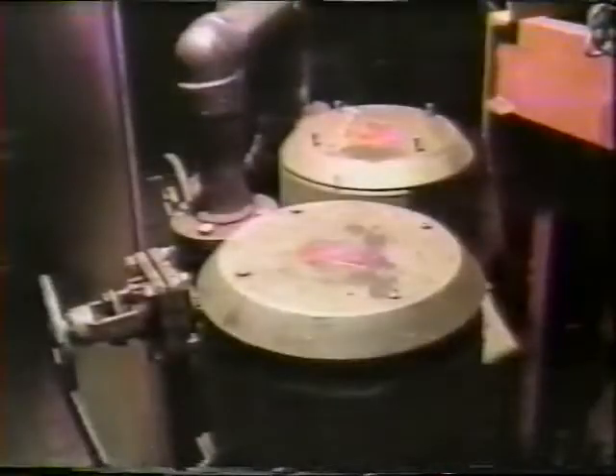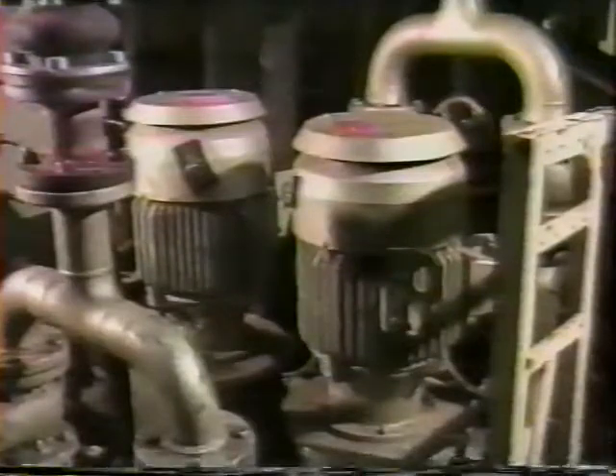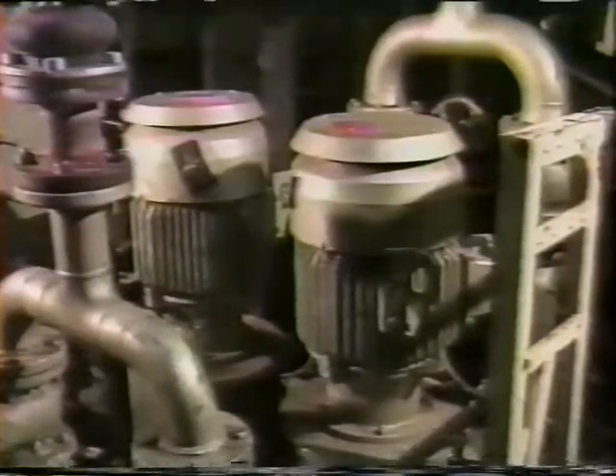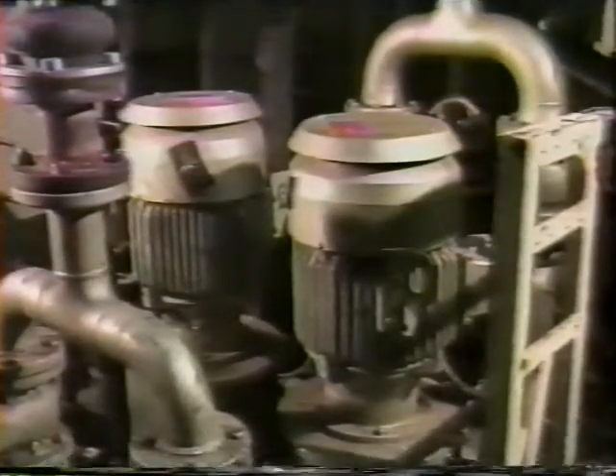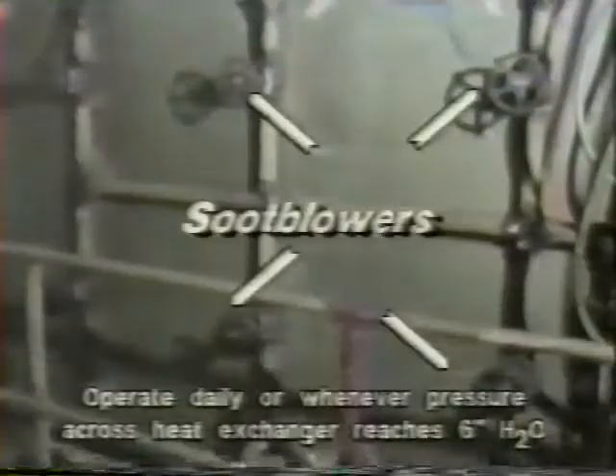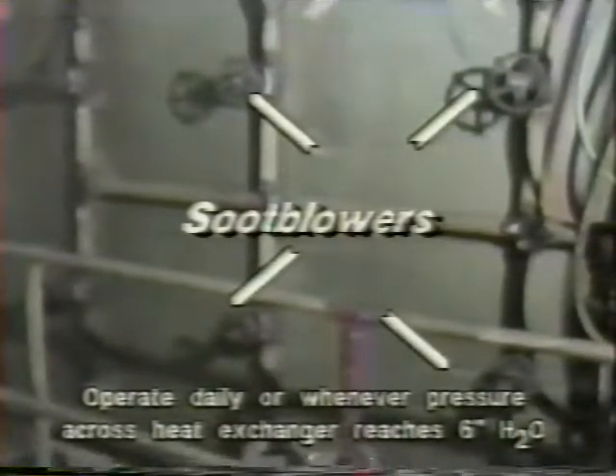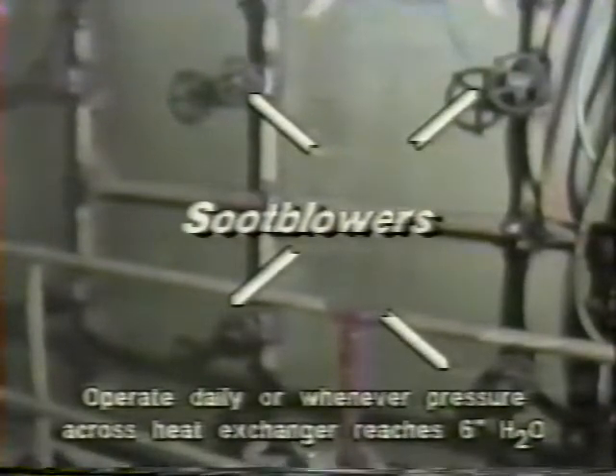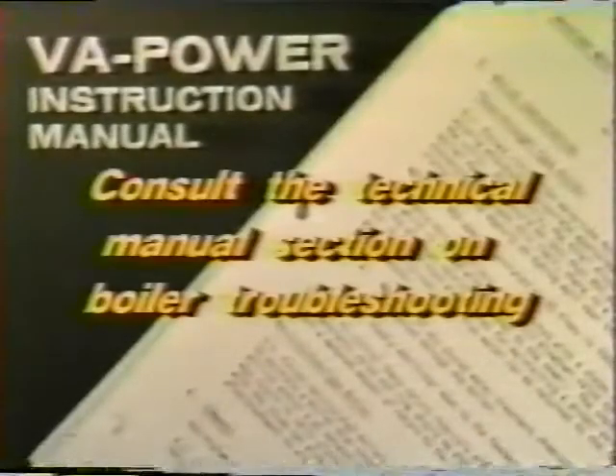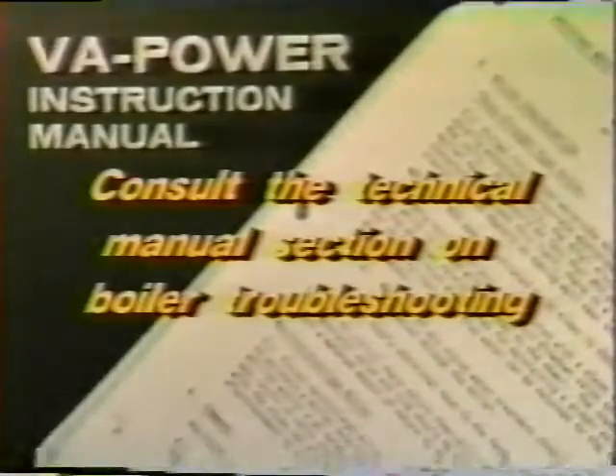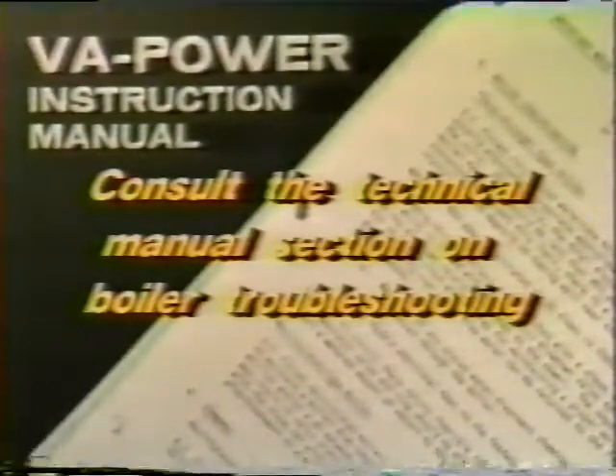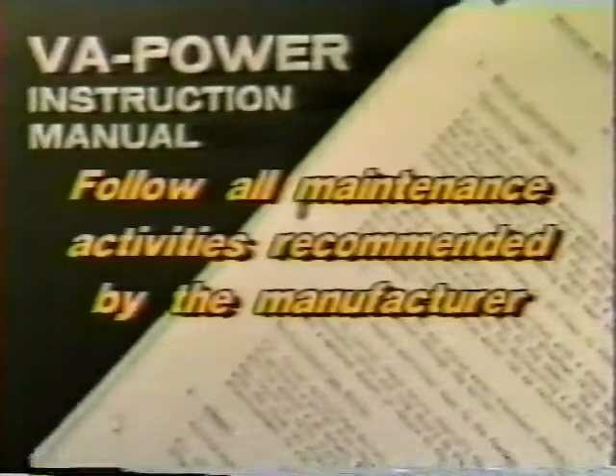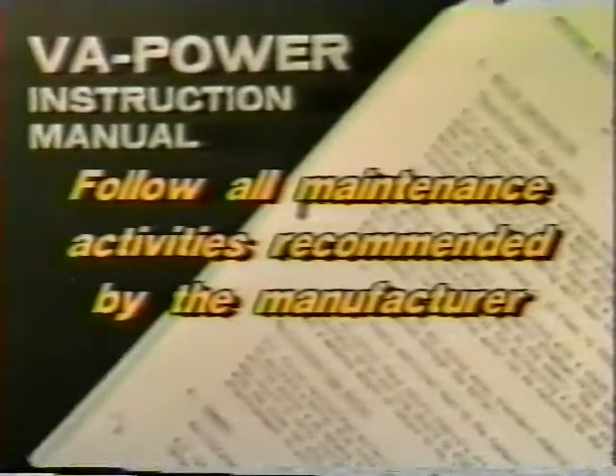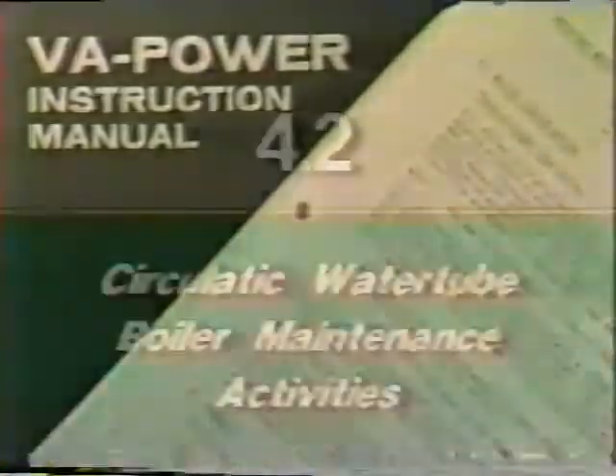Also, the number 1 and number 2 feed water pumps and recirculating pumps should be alternated so that each pump is kept in serviceable condition. Soot blowers on the boiler should be operated daily or whenever the pressure drop across the boiler heat exchanger reaches 6 inches of water. The tech manual contains a section on boiler troubleshooting that gives possible malfunction indicators along with probable cause of each malfunction. Carefully consult this section of the manual and follow all maintenance activities recommended by the manufacturer. 4.2.